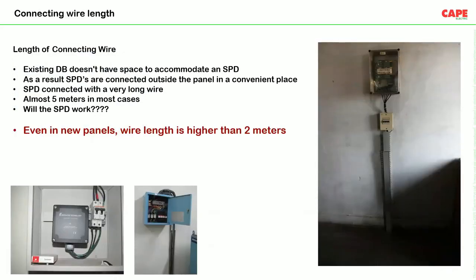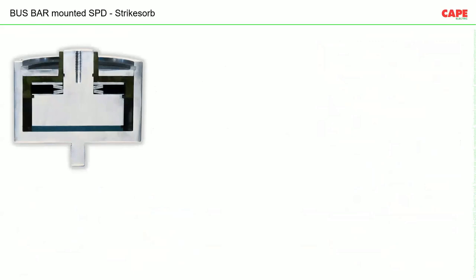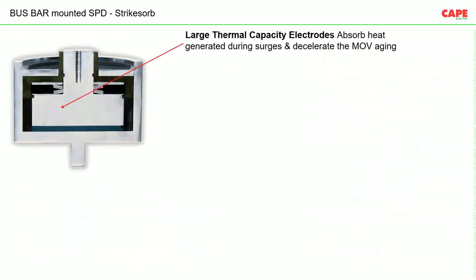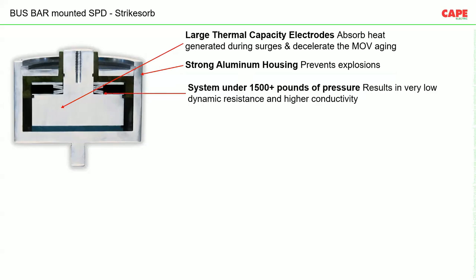Now, we have discussed the problem. What is the solution? One of the solutions is we use a bus bar mounted SPD or a V-type SPD, which can directly be mounted on the bus bar. So this is how a normal bus bar mounted SPD looks. These are the various advantages. It has very large thermal capacity electrodes to absorb the heat dissipation during the surges. Strong aluminium housing, to prevent any explosion in case there is a surge or the SPD is heated up or any other reason; if there is an explosion, the strong aluminium housing is going to protect.